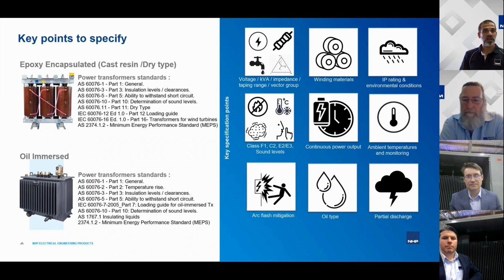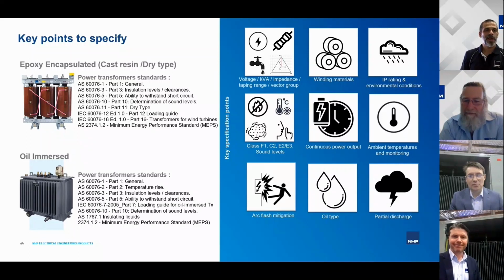Dimitri, did you want to elaborate on that point? Thank you. Yeah. So with the power output of transformers, it's probably evident to most people that whatever is on the nameplate of the transformer as rated power, this is what you should expect as transformer output in all conditions. And actually, the good thing is that it is the case when we talk about transformers on their own. So regardless if the transformer is within an enclosure or without an enclosure, it still must deliver 100% output, as per the 60076 standard.